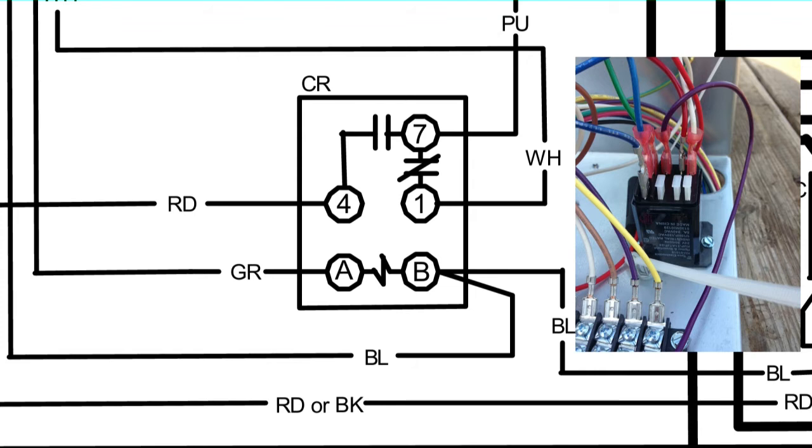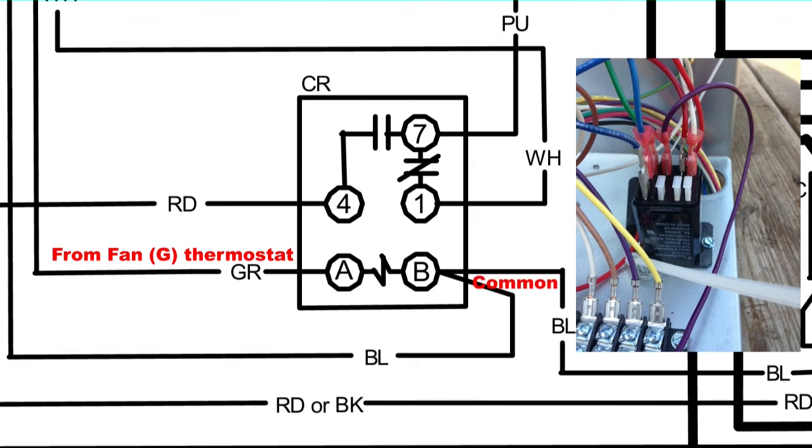You see a GR wire heading into the A—that is a green wire from the low voltage field connection. That wire is from the fan terminal on the thermostat. If you turn the thermostat to fan or to heat or cool for a heat pump, it will send that green 24-volt to that A. On the B side, that is your common, typically blue.